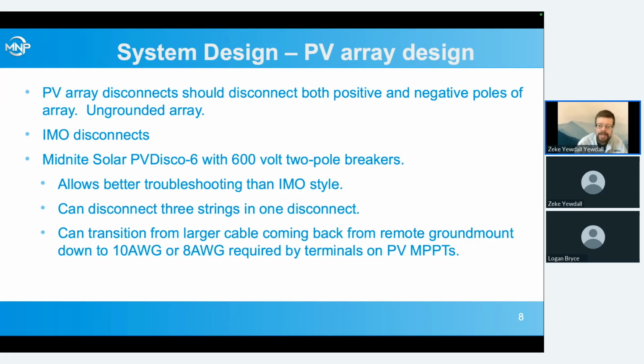A nice thing about having a disconnect, especially the MidNite Solar ones that can take larger wire, is if you've got larger cable coming back from a remote ground mount that's bigger than 8 gauge, 8 gauge is the largest you can put into the terminals on the all-in-one inverter. You can use that disconnect to transition from that large cable coming back to some 10 gauge or 8 gauge for the last little jump into the building and over to the all-in-one inverter.